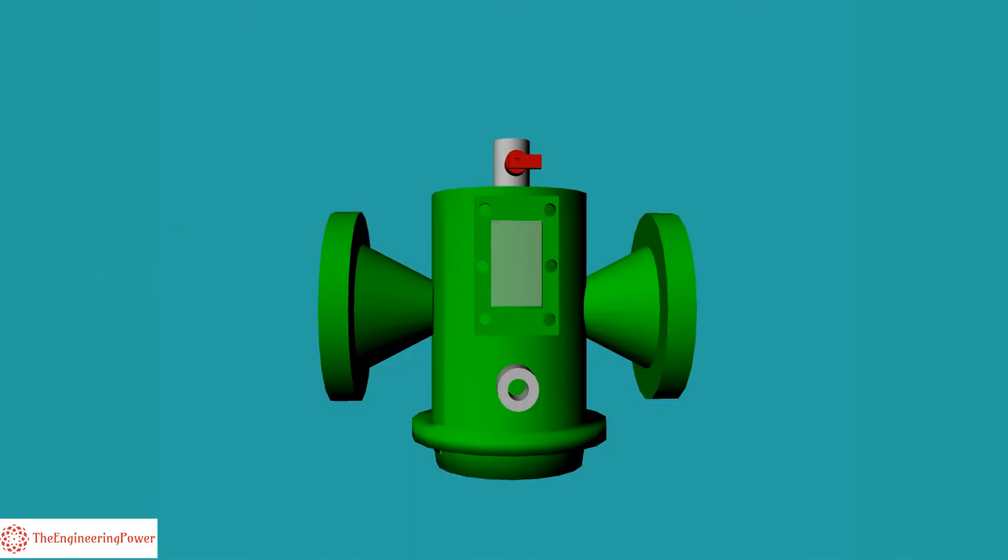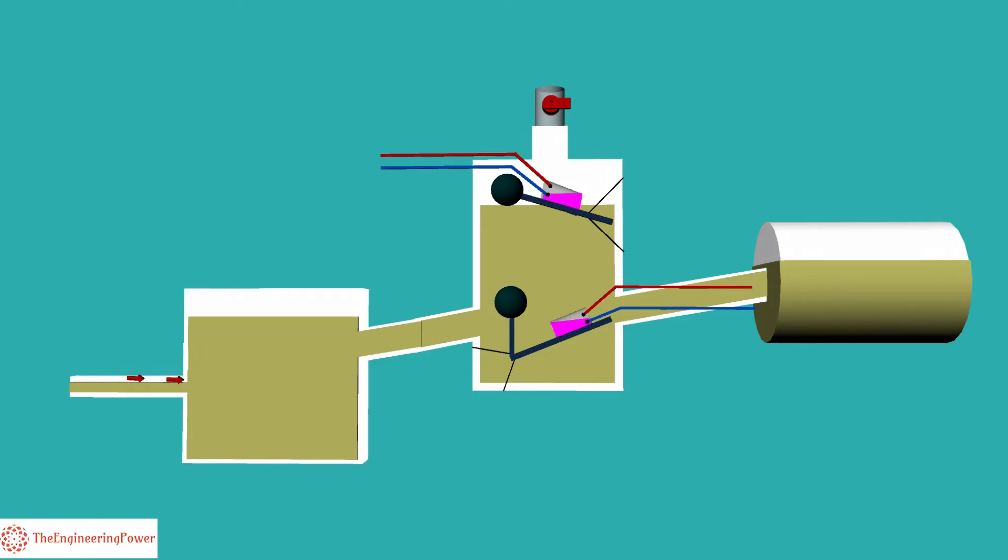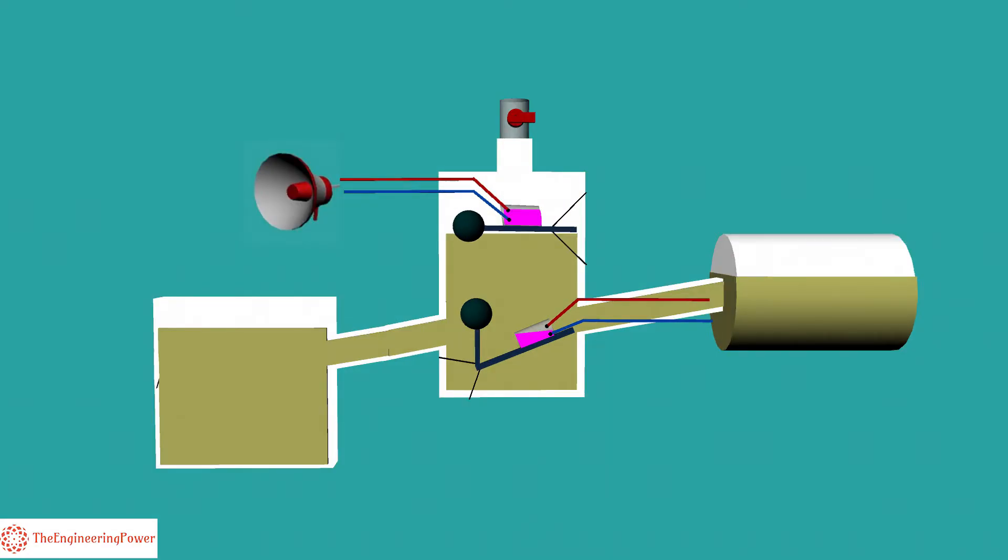In some cases, Buchholz relay may be operated even without any fault inside the transformer. We call it false operation of Buchholz relay. For example, when oil is added to a transformer, air can mix up with oil under the relay cover causing a dip in oil level and resulting in false Buchholz relay operation.